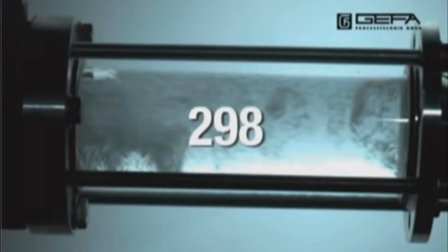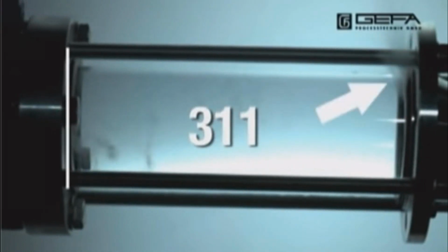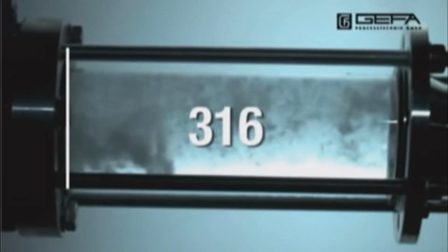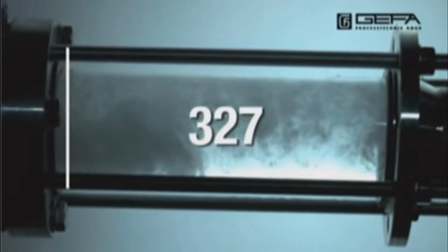Consequences of water hammer effect. In slow motion, you see how water spray squirts out of the flange gasket area. The studs are stretched, and at the same time the whole construction is spoiled with a deflection of 50 millimeters.